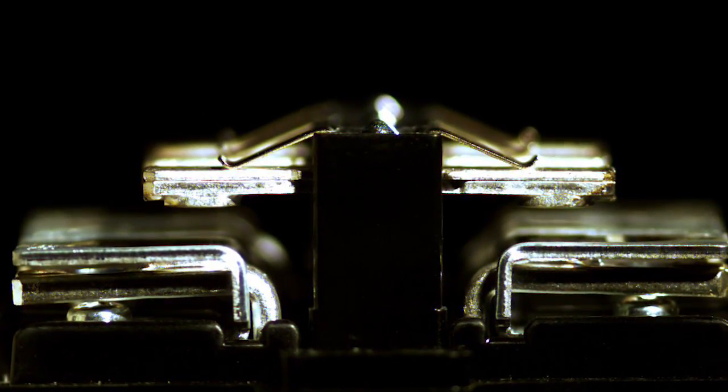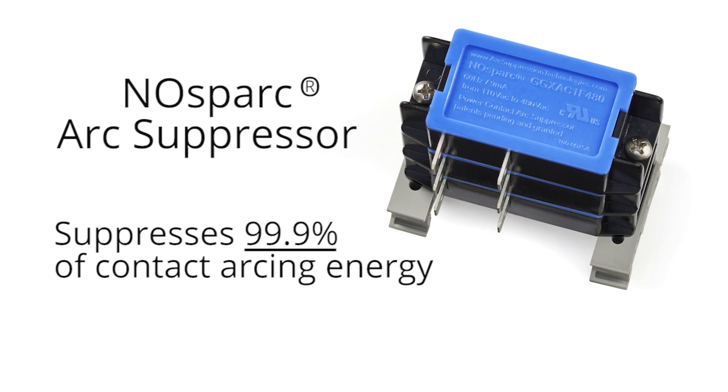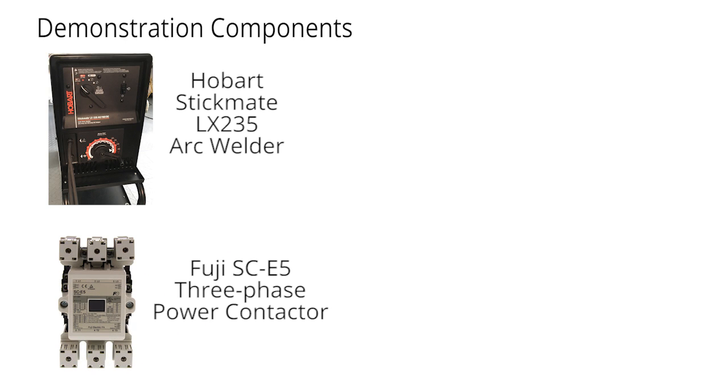We think you'll be surprised by the damage that arcing inflicts on contact surfaces even after just a few cycles. We also believe that you'll be impressed by the powerful protective ability of NOsparc arc suppressors. These patented solid state devices suppress at least 99.9% of the contact arcing energy, which keeps your contact surfaces looking new and enables your power contactors to last at least 10 times longer.